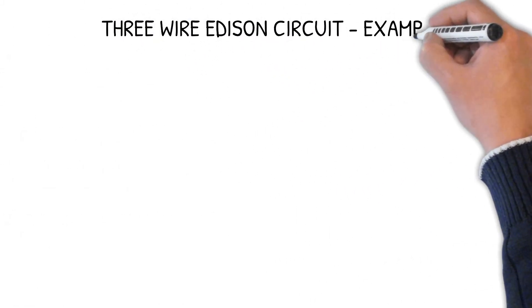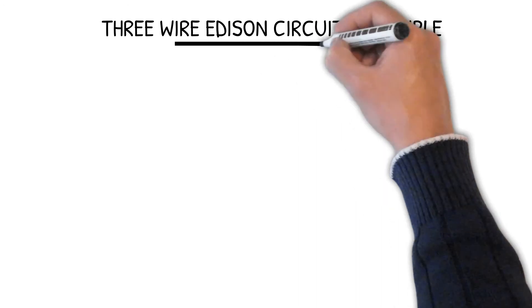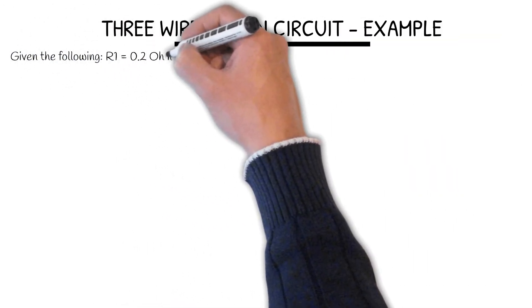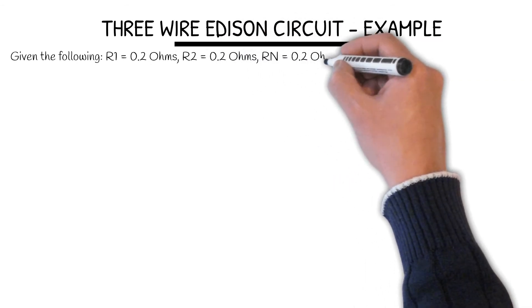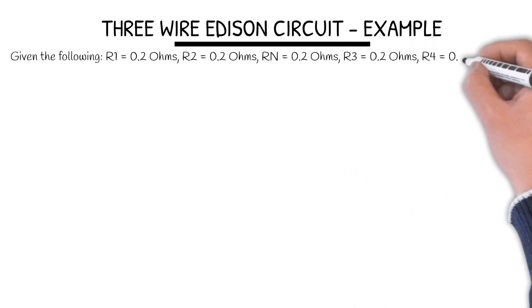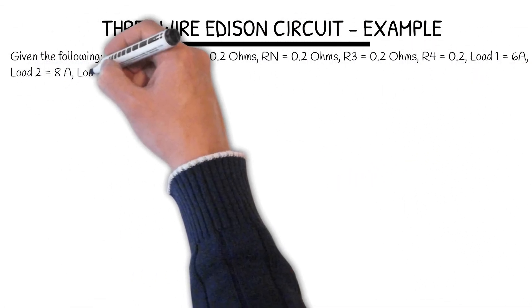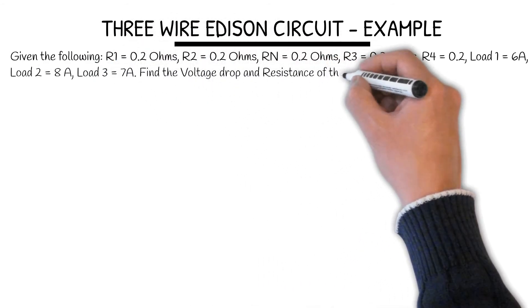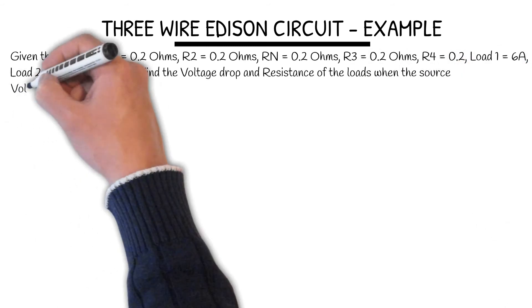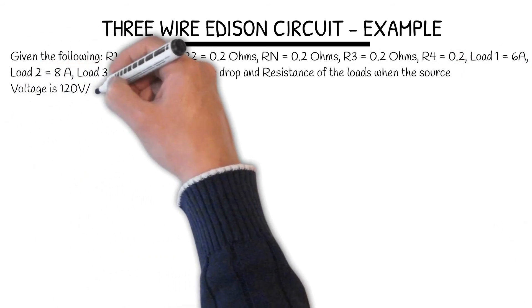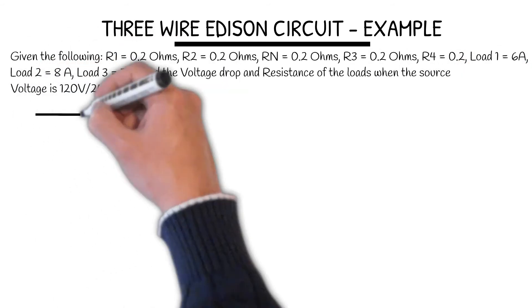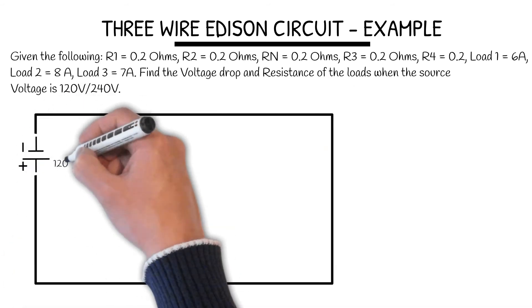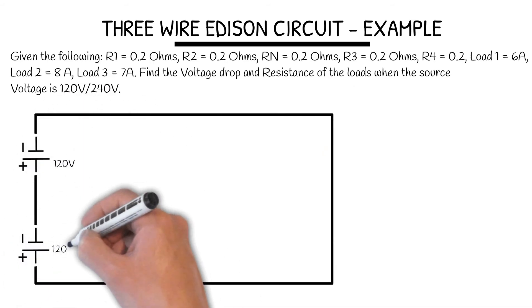3-Wire Edison Circuit — one last example. Given: all resistors have 0.2 ohms of resistance, but this time we have two sources and three loads. Load one is 6 amps, load two is 8 amps, load three is 7 amps. Find the load volt drop and resistance when the source voltage is 120/240 volts. This example is a little different — we have a 240-volt load as well.